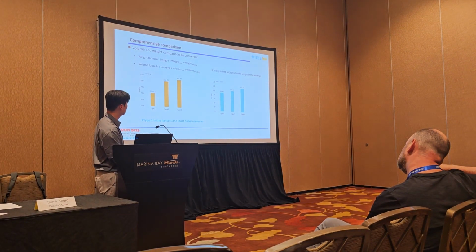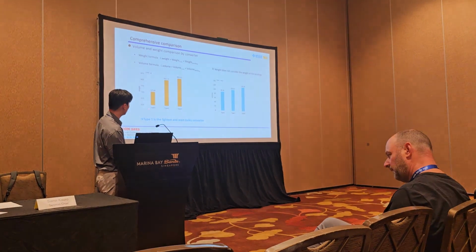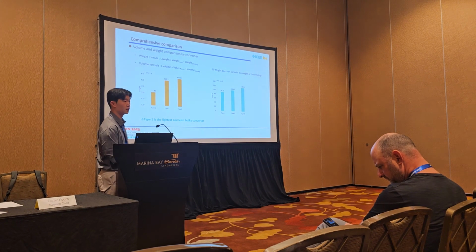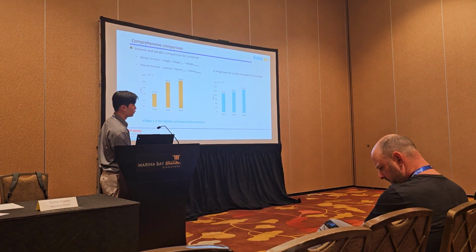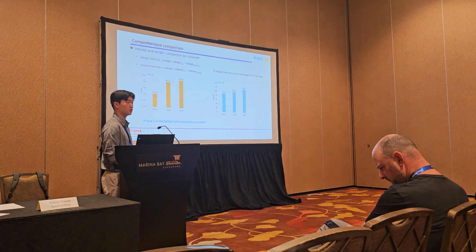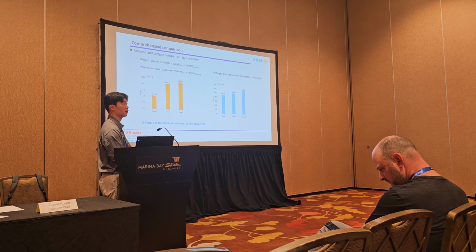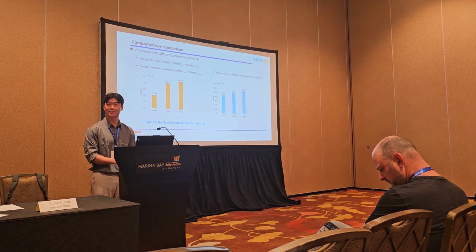So if you focus on weight and volume, you had better choose type 1. It's the lightest and least bulky converter. But if you focus on reliability or efficiency, you had better choose type 2, which uses magnetic components. They are more reliable, the magnetic components.